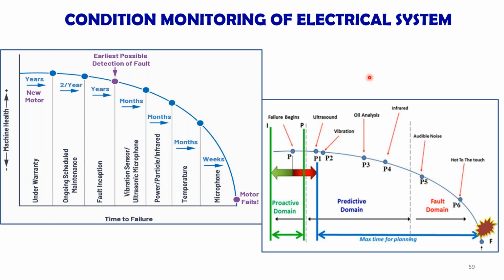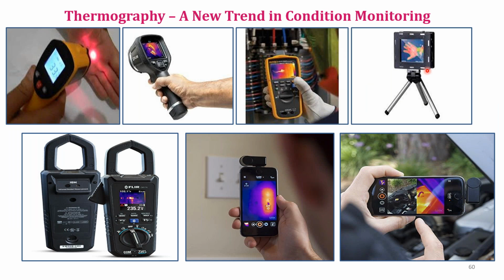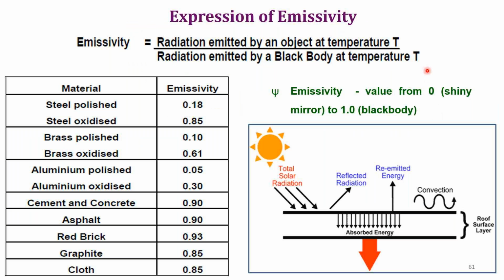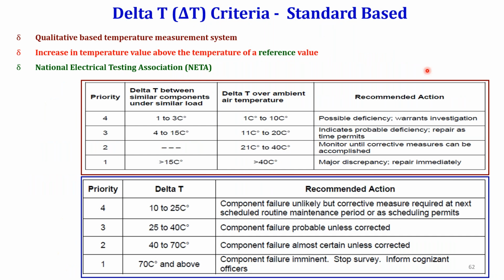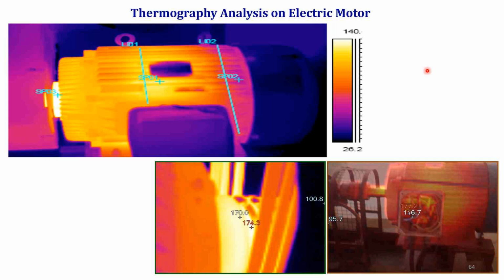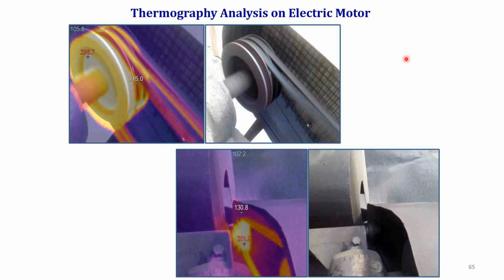And these are some of the condition monitoring methods. Of course, this is not an energy conservation method, but it is condition monitoring. As you know, the thermograph is a very good tool for condition monitoring of the system. Of course, this also will have a good impact on the savings in the system. So you can continuously monitor the motor and all electrical equipment temperature, and check whether the temperature is within the limit or not. And if it is at a very high level, then based on the rule or the standard, you have to take the proper decision to address the problem.